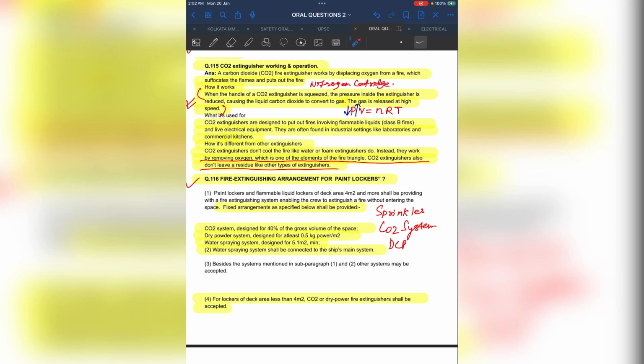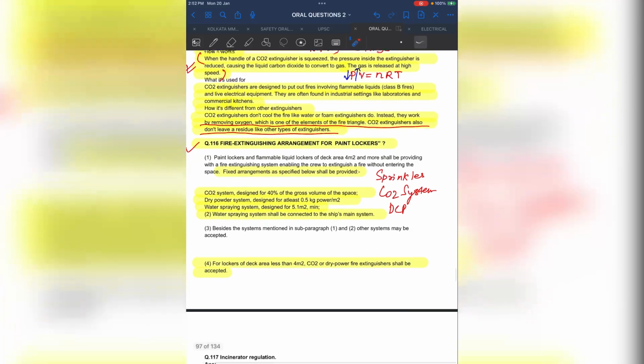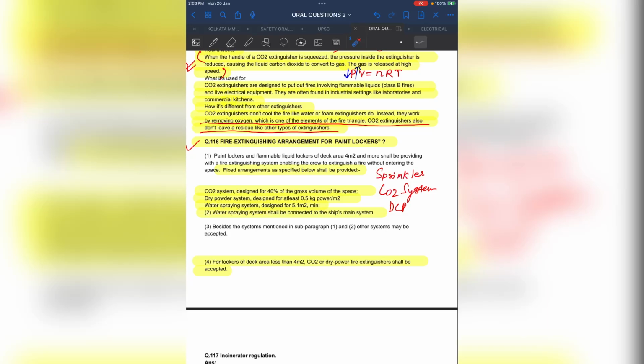Okay. So, how does it work? The CO2 extinguisher has a safety pin and a handle. When you remove this pin and squeeze this handle, the pressure inside the extinguisher is reduced, and due to this reduced pressure, the volume will increase. So the pressure inside the extinguisher is reduced, causing the liquid carbon dioxide to convert to gas. The volume expands as it converts from liquid to gas, and then the gas is released at a very high speed to extinguish the fire. Okay. So, I already explained the working also. Let us move to another question.